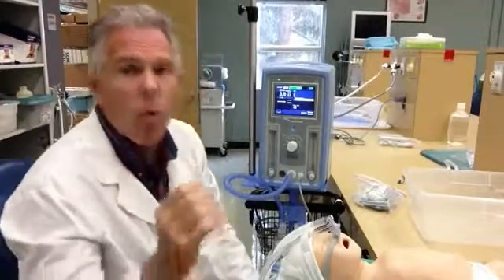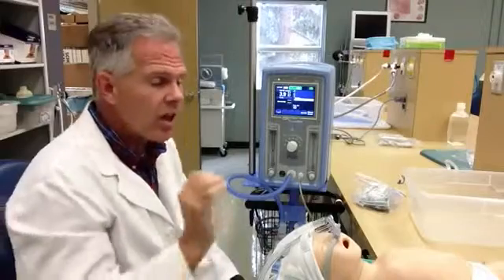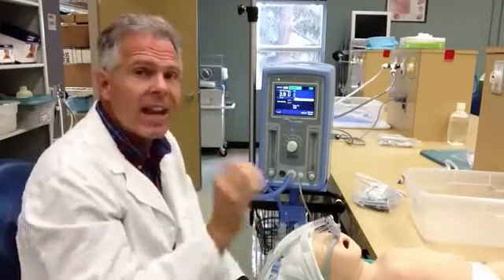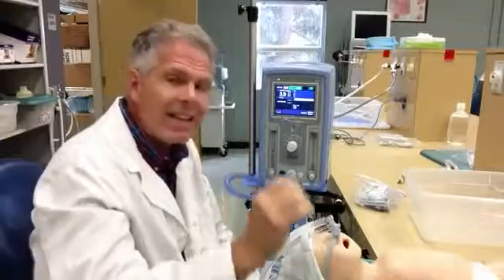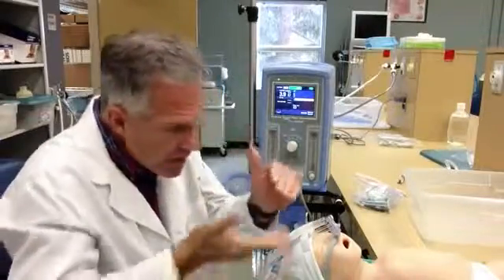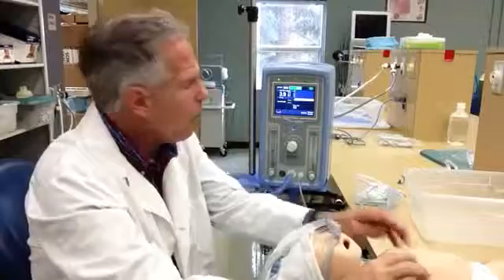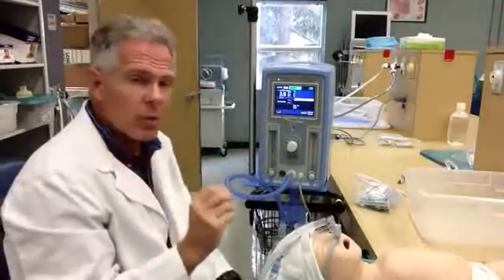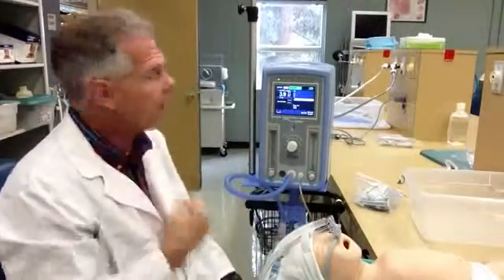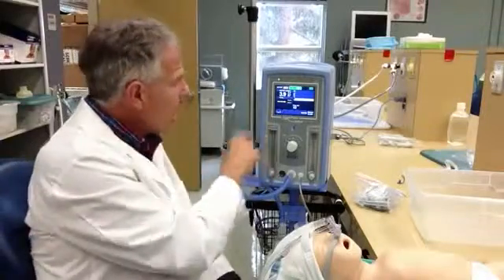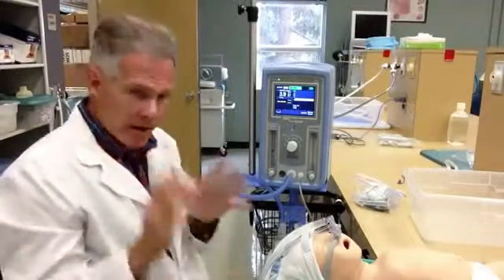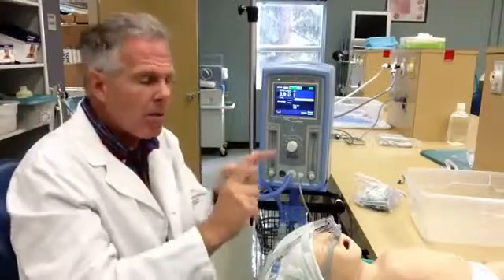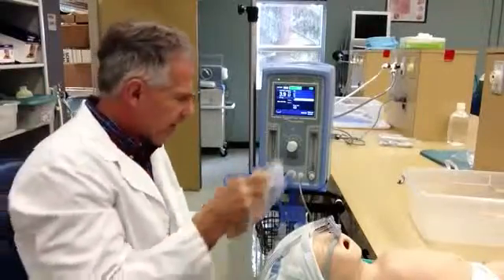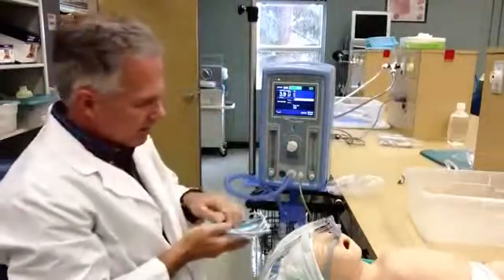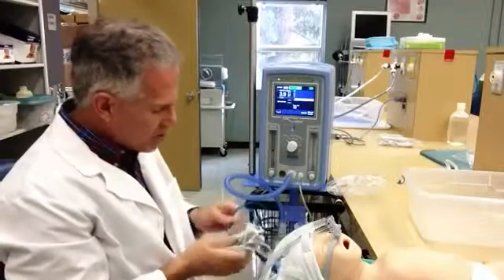Okay? That's actually one of the huge advantages of this mechanical ventilator. It gives very effective nasal CPAP. Even when the patient's breathing in and out, it synchronizes very well with them, and you don't see much fluctuation in the CPAP pressures delivered at the back of the pharynx. Adjusting that with the flow. So we've got nasal CPAP, we've got straight IMV, and it does have the option on this mechanical ventilator to synchronize the mechanical breaths with the patient.